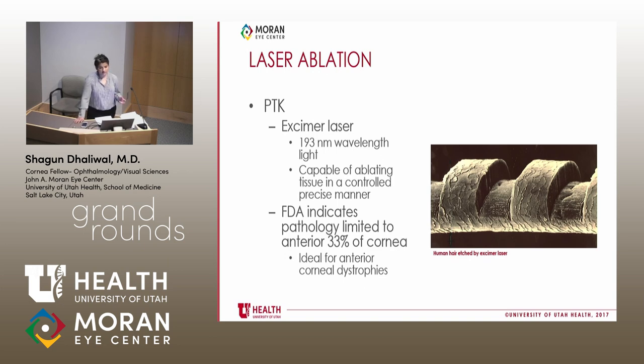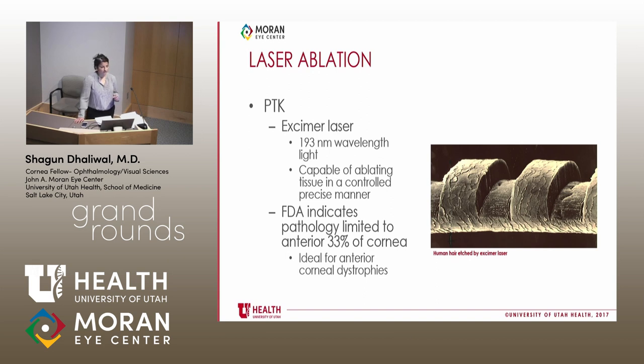Moving into laser ablation — with the advent of the excimer laser in the 1980s and 1990s, this has become the most popular treatment option. The excimer laser uses 193-nanometer wavelength light and is capable of ablating tissue in a very controlled and precise manner. That ability to precisely titrate the laser is what makes it perfect for anterior corneal dystrophies. The picture shown is a human hair that has been etched by the excimer laser to illustrate its precision.